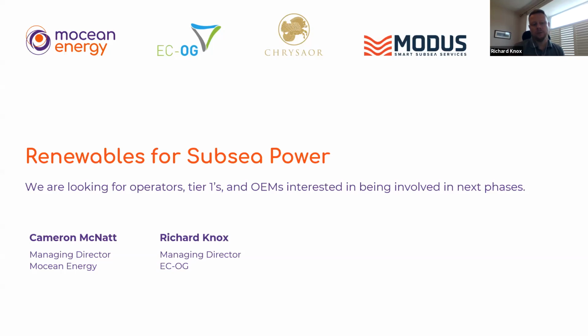There was a question about the size of it. The battery system we've installed or specced up for the trials is 150 kilowatt hours, and Cameron showed the optimum size is 500 kilowatt hours. The skid shown in the slides earlier can handle roughly 800 kilowatt hours physically within that 2.9 meter wide skid. But the actual overall architecture can take up to 2.7 megawatt hours, which is what the IAMS is capable of controlling.